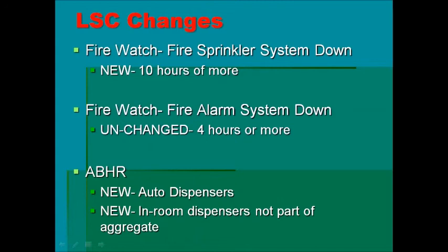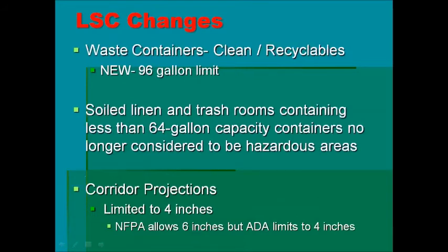When it comes to alcohol-based hand rub devices, there are new compliance elements regarding the volume of alcohol-based solution allowed within a smoke compartment. The rule is you can have no more than 10 gallons of total volume of alcohol-based solution in any single smoke compartment - but here's some good news: the volume that counts toward that 10 gallons is only what's in dispensers in common areas or hallways. If you've got ABHRs in resident rooms, which you're allowed to have up to one, that amount does not figure into the total 10-gallon aggregate. So make sure you're familiar with that.